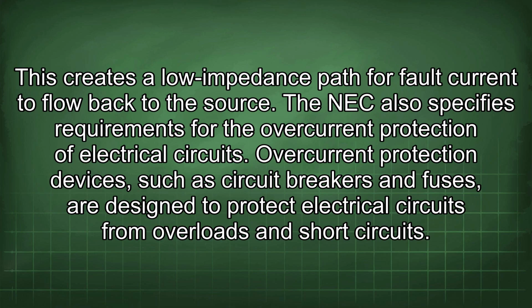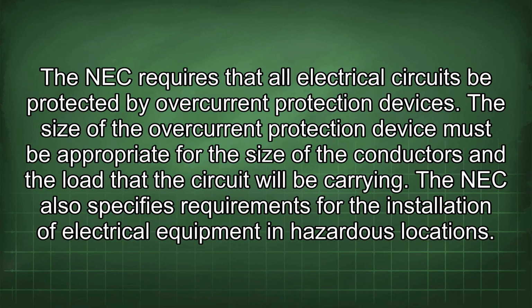The NEC also specifies requirements for the overcurrent protection of electrical circuits. Overcurrent protection devices, such as circuit breakers and fuses, are designed to protect electrical circuits from overloads and short circuits. The NEC requires that all electrical circuits be protected by overcurrent protection devices. The size of the overcurrent protection device must be appropriate for the size of the conductors and the load that the circuit will be carrying.